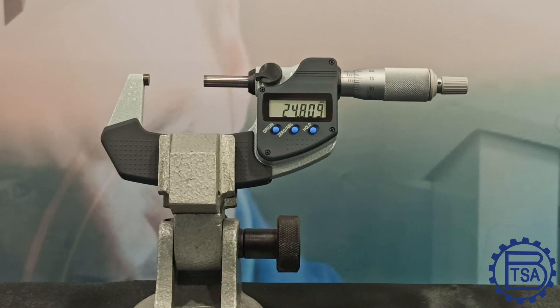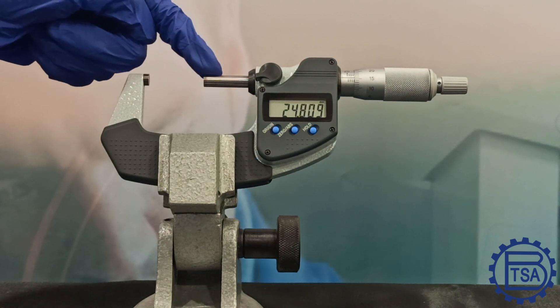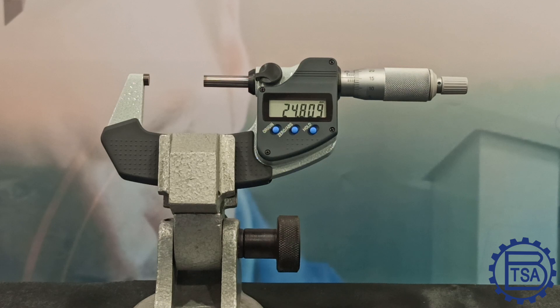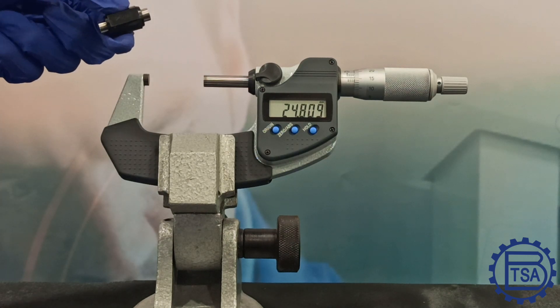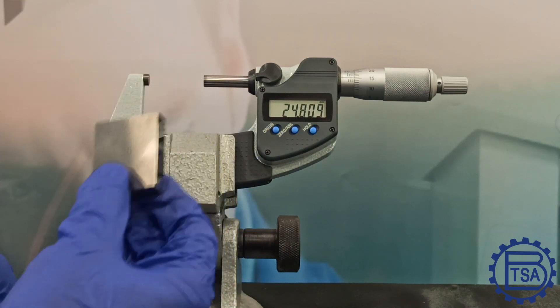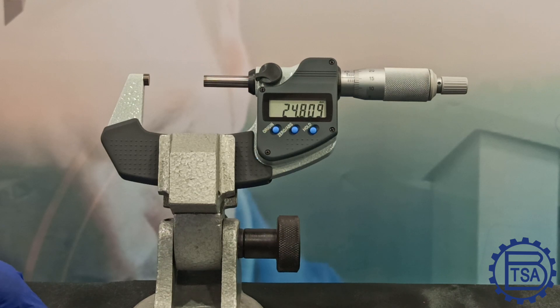In larger micrometers, the anvil and spindle do not come in contact with each other. In such micrometers, setting rods or slip gauges can be used, but make sure that the value is taken from the calibrated certificate and not from the gauge.